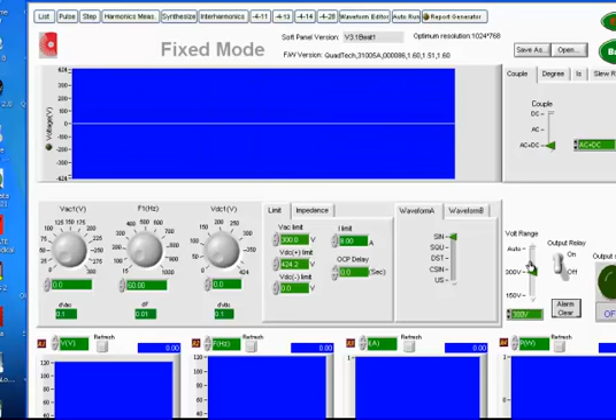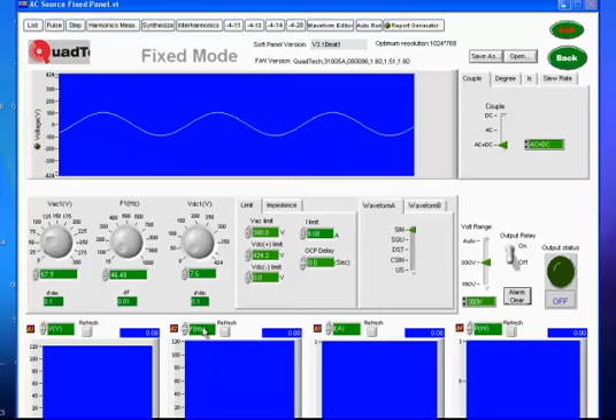As I'm doing this demo and adjusting the values, these values are automatically appearing on the AC source. As well, we are able to monitor voltage, frequency, current, any one of the parameters such as power factor, crest factor, DC voltage, DC current, peak current, reactive power, or total VA, or just straight power. Once we select what we'd like to see, for example, let's select power. We want to select voltage, current here. We would turn the output relay on and turn the output on.